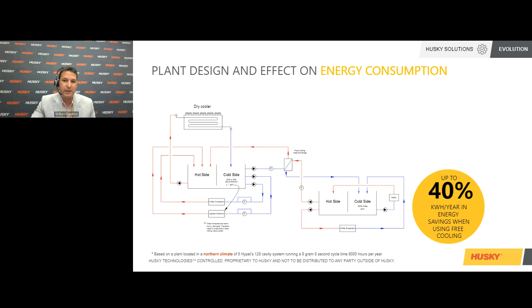Water is not an energy consumption, but it's also part of your utilities. Tower waters here in North America are very common. We find that installing dry coolers are a better option because you're not consuming as much water as a cooling tower. There is no water evaporation, so with a dry cooler your water consumption is minimum.